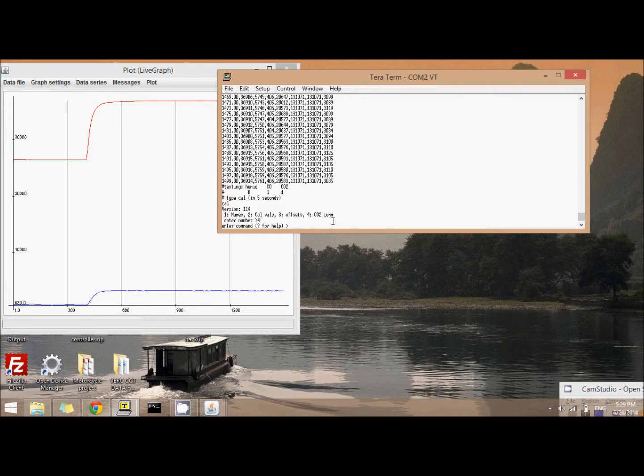And all we need to do is tell it that it is looking at 3,000 ppm of CO2, and it'll be able to zero itself from there. So the command for that is capital X space 3,000 for 3,000 ppm. And after that, all we have to do is hit enter. It gives us a response back. It looks okay. And then we just have to disconnect the gas, which we'll show you in the next step.